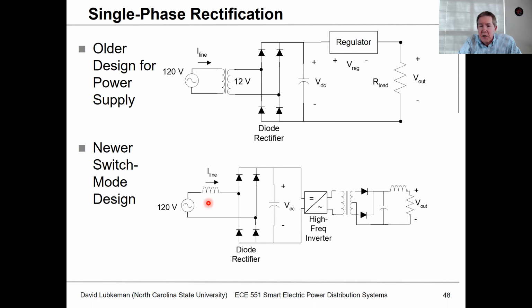What you would have is you would just simply have a line impedance, and then it goes through a direct AC to DC conversion. And then basically what you do is you convert the DC back to, say, AC again, and then if you need the DC, you can go ahead and rectify this and convert back to DC. So this is another type of design that you would see more for laptop power supplies or computer power supplies.